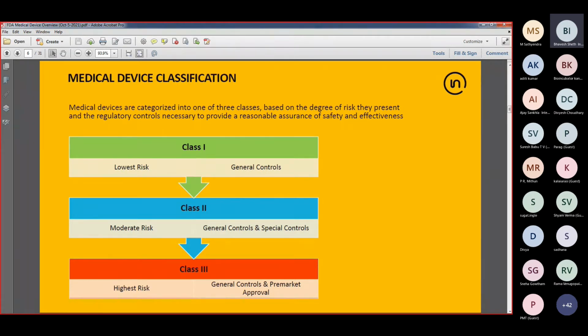Class 1 medical devices, as you'd assume, are the lowest risk devices, and only the general controls are applicable. For class 2 devices, we have products that tend to present moderate amount of risk. And for those kind of devices, general controls and special controls are applicable. And the last is the class 3, which is for the highest risk devices, life-supporting devices, life-sustaining devices, in which case general controls are applicable, but also a formal pre-market approval is required. Now we'll get into more detail about the actual submission types after finishing up the classification section. But in a nutshell, these are the main categories you're looking at.